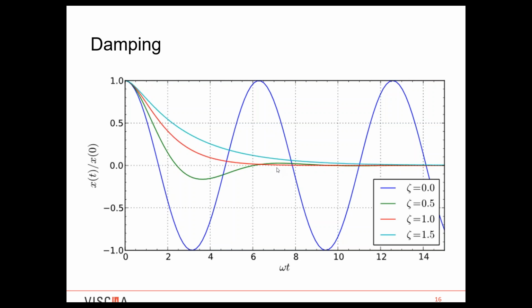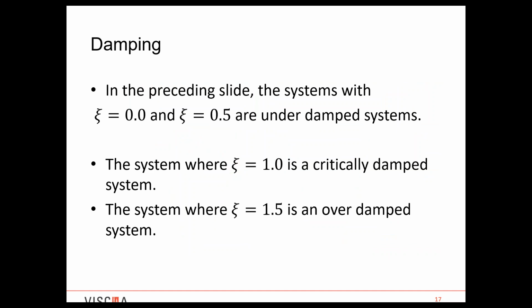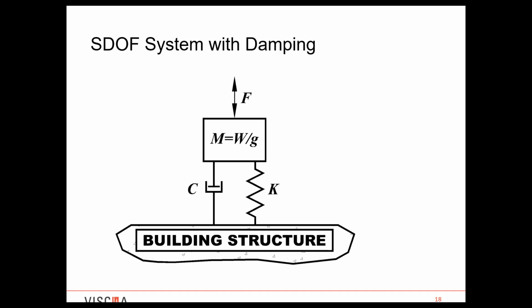And really your cyan or turquoise line here, we would consider that overdamped. You're not going to get an additional advantage as far as isolation efficiency when you're over that damping ratio of 1. In this example, that turquoise line is 1.5 damping ratio. So again, as I mentioned, those that were at 0 and 0.5 were underdamped systems. And that system at 1 is ideally what your goal is to shoot for, the critical damping ratio of 1. And obviously where it was over 1.5, it's an overdamped system, and you're not getting much advantage for having that additional damping. You're not going to see it in the isolation efficiency. So I mentioned earlier a single degree of freedom system.